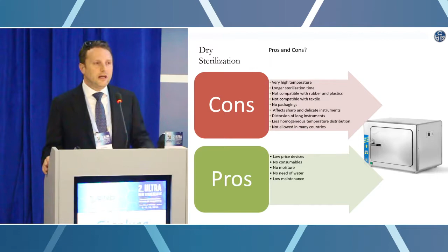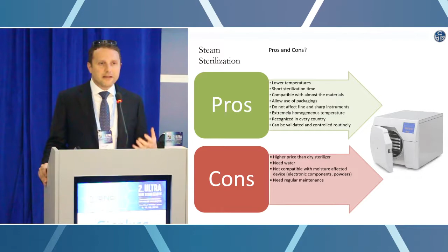And of course, the heat distribution is also not as precise as in a small benchtop steam sterilizer. On the other hand, the small benchtop steam sterilizers, the autoclaves, work with water, so at least you need a source of demineralized water. They need regular maintenance. They are not so complicated to use, but anyhow, when you are purchasing a benchtop sterilizer, you always have to consider that you have to carry out regular maintenance on them.